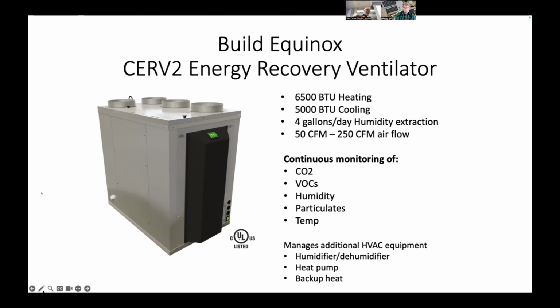So I can actually bump heat and or cooling into the air instead of just tempering what's coming in from the outside. Because if I'm exhausting 72-degree air out and I run it through a passive heat exchanger, I can temper the incoming air. But if it's 0 outside and I'm exhausting 72-degree air, somebody help me with the thermodynamics, right? So the incoming air ends up coming up to maybe 55 or 60. That's relatively cool to be sitting next to. With this unit, I can actually bring it back up to indoor air temp. So I can do about 6,500 BTU of heating.